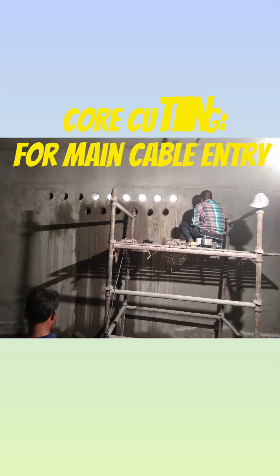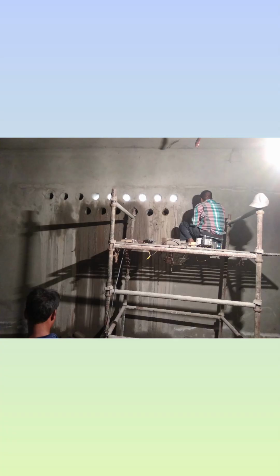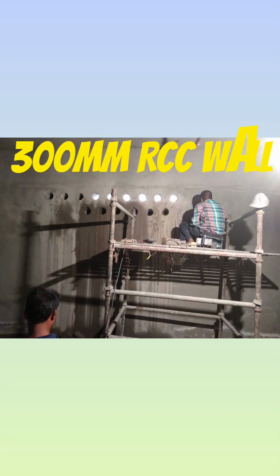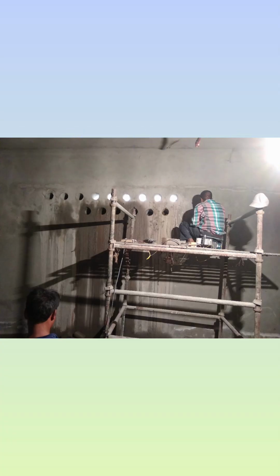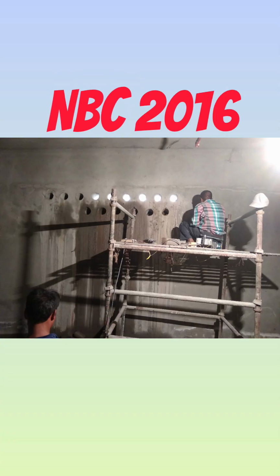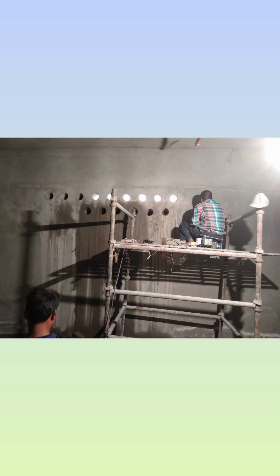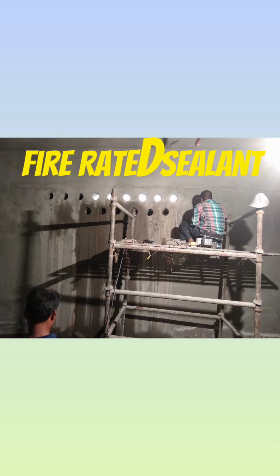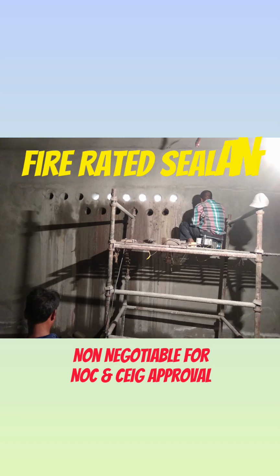Here, technicians are creating openings in a 300 RCC wall for cable entry. This work was executed only after approval of the coordinated service drawing. As per NBC 2016, all wall penetrations must be sealed with a 2-hour fire-rated sealant post-cable installation. This is a non-negotiable requirement for fire NOC and CEIG approval.